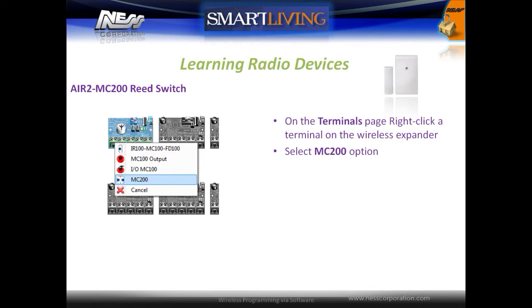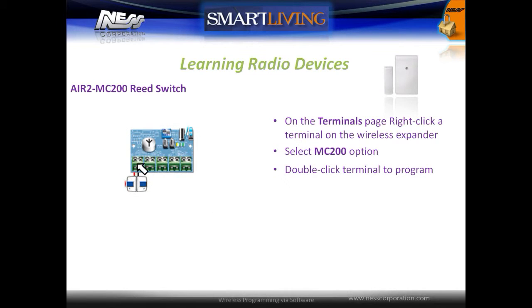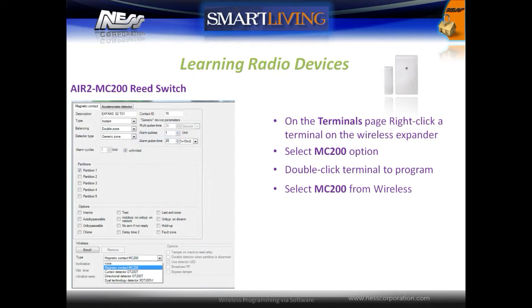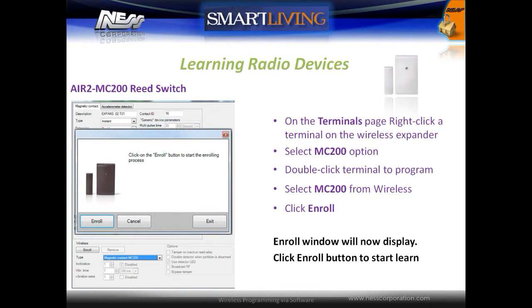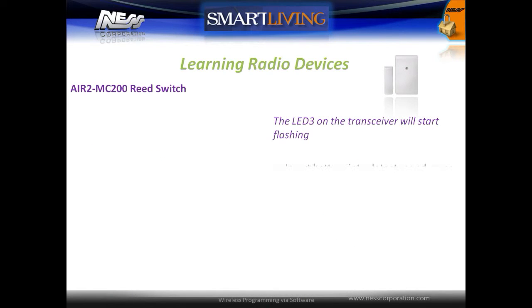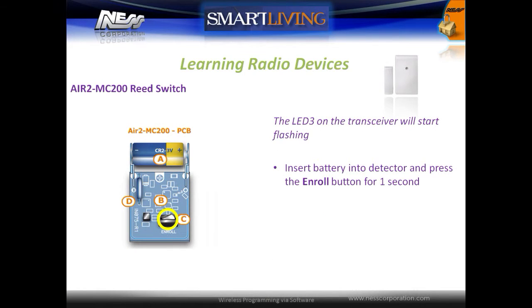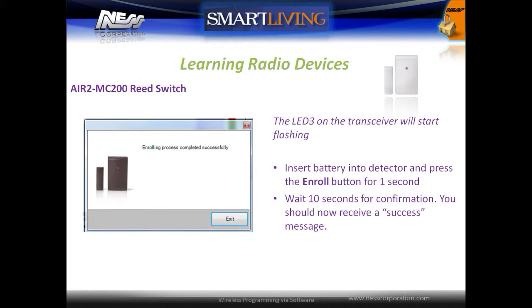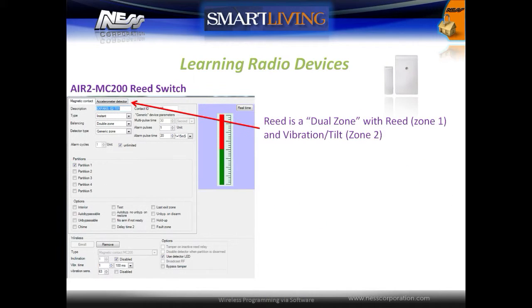To program this device, on a wireless terminal right click and select the MC200 option. Double click on the terminal to open the configuration window. Under the wireless configurations, select the MC200 option and then select the enroll button. The transceiver's LED 3 will start to flash — insert the battery into the device and press the enroll button for one second. You should receive a learn confirmation after about 10 seconds. The MC200 is a dual zoned device with the reed switch on zone 1 and the vibration and tilt sensor on zone 2.